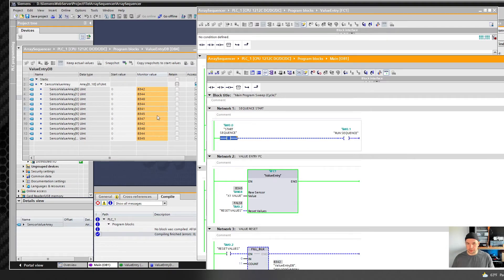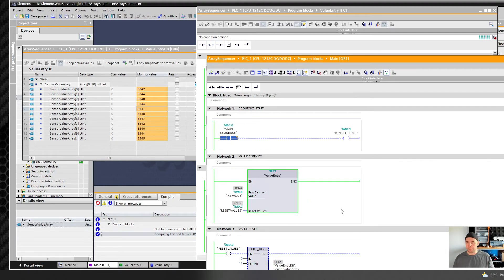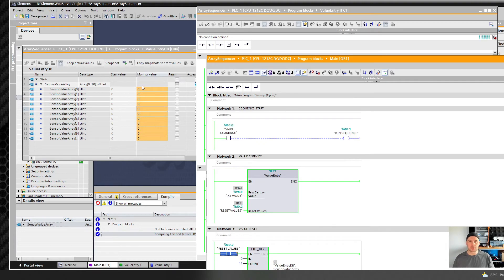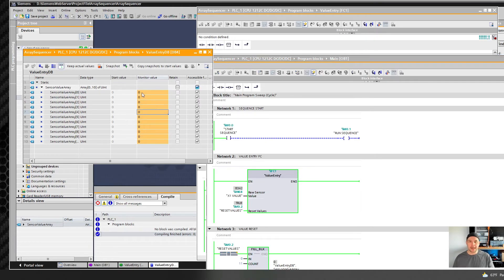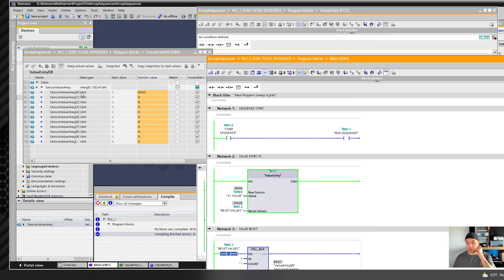I'm going to stop the sequence — it stopped at index five. In my use case I was doing this for an eight-hour shift and I don't want to start at array index five; I want to start at zero. So if I do a reset, it zeros out the array using the fill block and resets the counter back to zero. Now when I modify the start it's back at index zero with all values cleared, ready to go again.